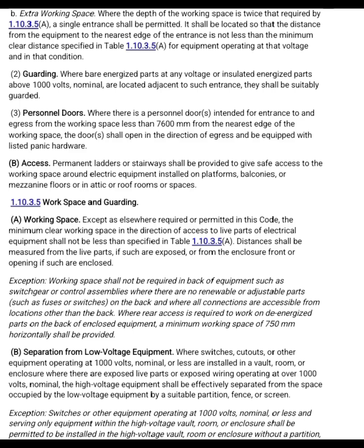1.10.3.5 Workspace and guarding. A. Working space. Except as elsewhere required or permitted in this code, the minimum clear working space in the direction of access to live parts of electrical equipment shall not be less than specified in Table 1.10.3.5a. Distances shall be measured from the live parts if such are exposed, or from the enclosure front or opening if such are enclosed. B. Separation from low voltage equipment, where switches, cutouts, or other equipment operating at 1000 volts nominal or less are installed in a vault, room, or enclosure where there are exposed live parts or exposed wiring operating at over 1000 volts nominal, the high voltage equipment shall be effectively separated from the space occupied by the low voltage equipment by a suitable partition, fence, or screen.